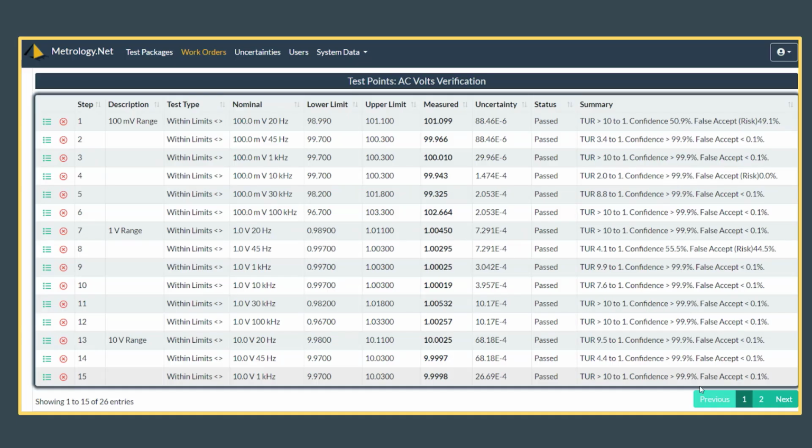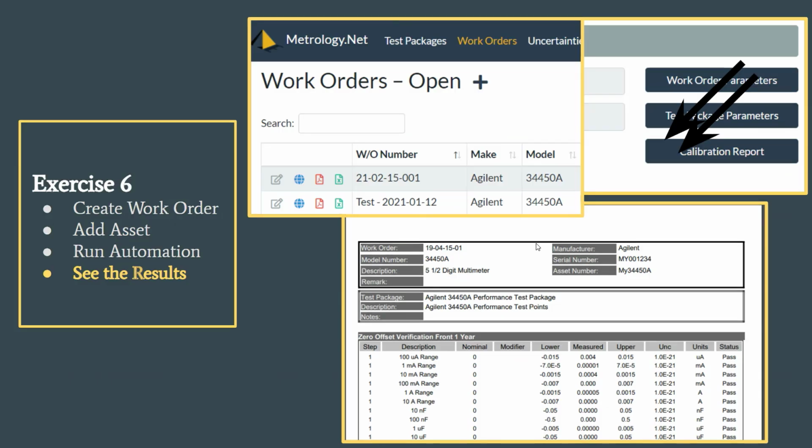And then it will run through all the calibration. You can see that when we put this training together, we didn't have the check with the 17025, so that wasn't available yet. So then when we're done, we want to see the calibration data. We've got a calibration report here, and we can pull up all of our calibration data.